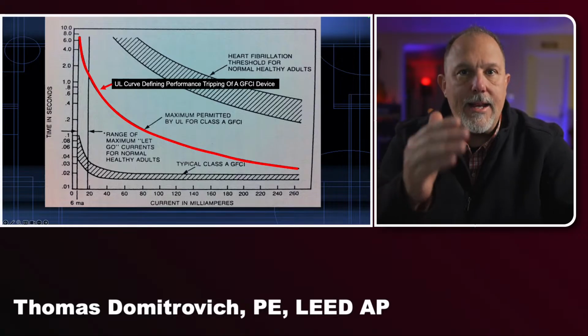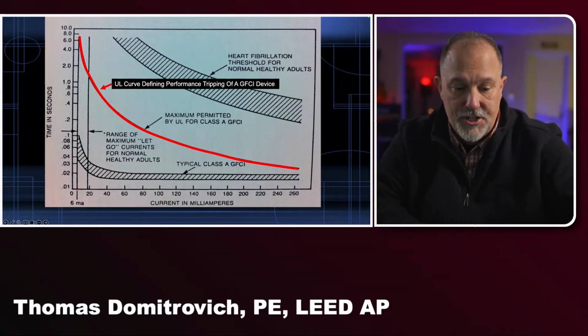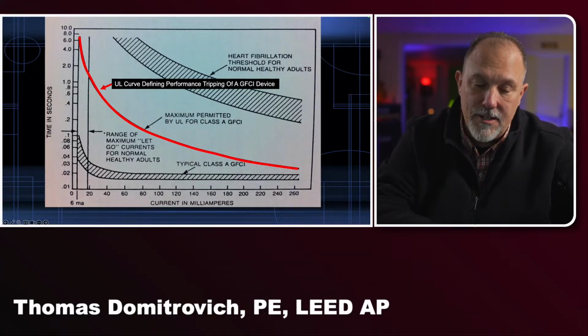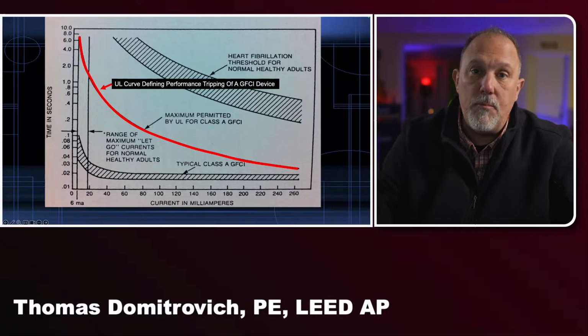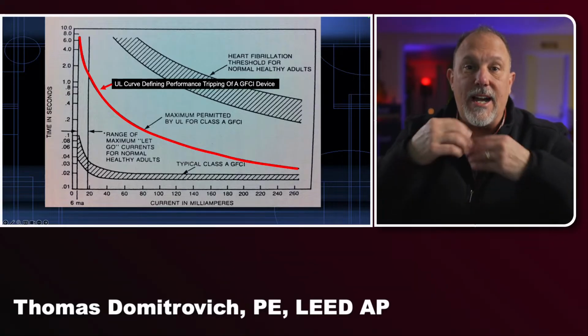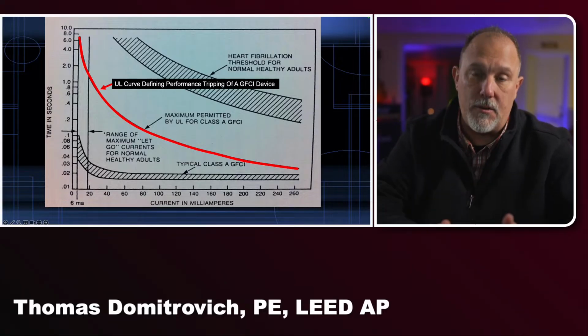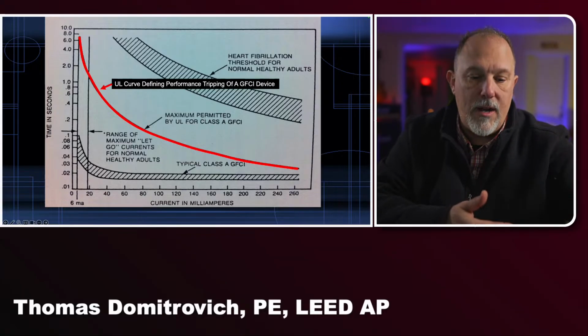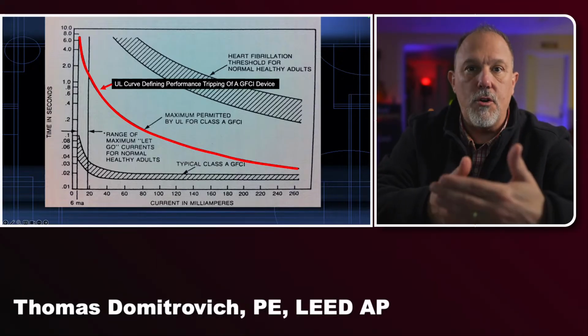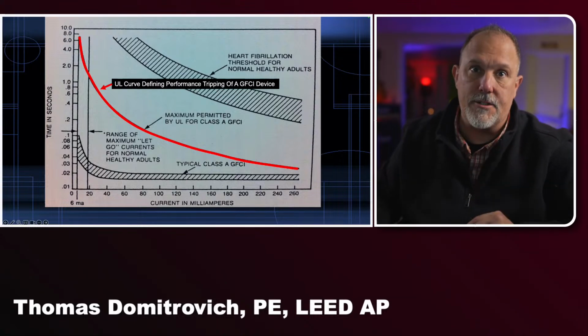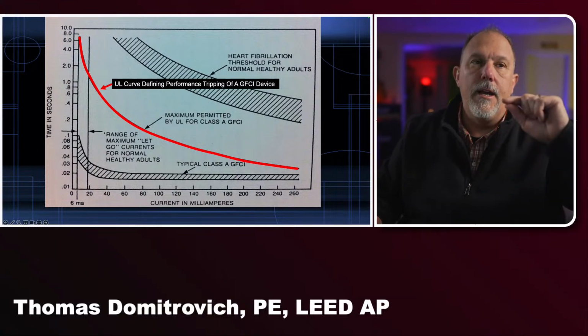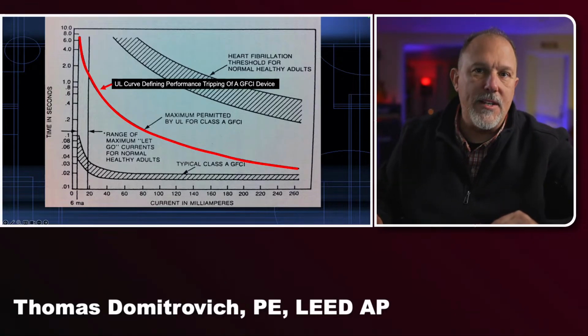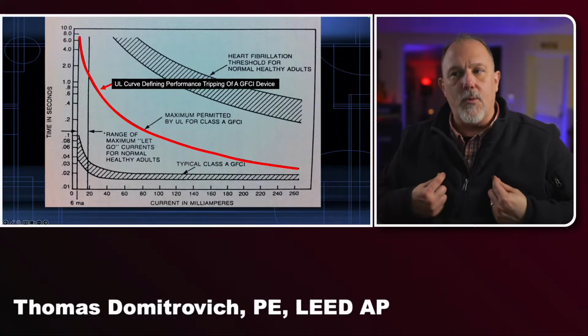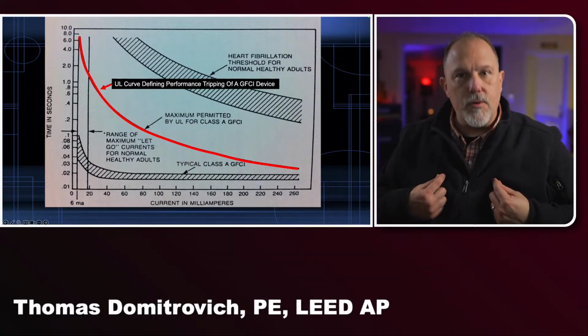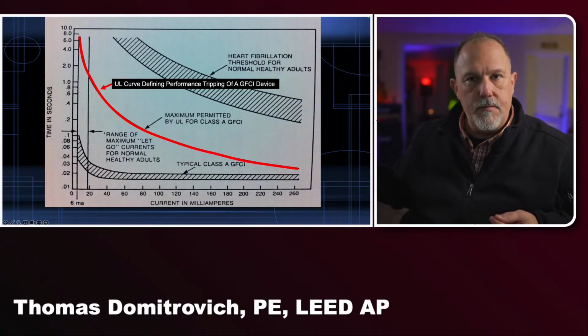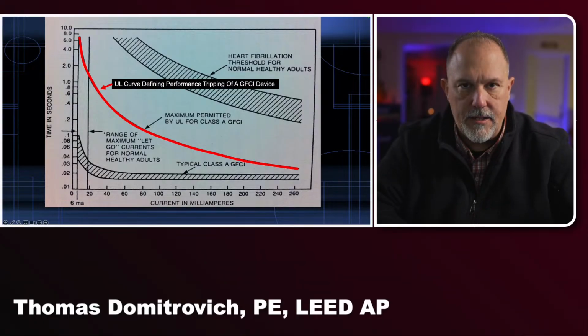And I can understand that from a design perspective, a design engineer arguing with marketing and sales saying, we need to require pulling a neutral to our appliance because I'm going to be filtering off these higher frequency ground fault currents, and I don't want them to be a ground fault current. I need them to be a current that goes over a normal path, which is the neutral, the grounded conductor. And you're going to lose that battle every day of the week, twice on Sunday, because they're going to go, you mean to tell me that I need to require a neutral conductor and none of my competitors need to? So high frequency is one of these aspects.